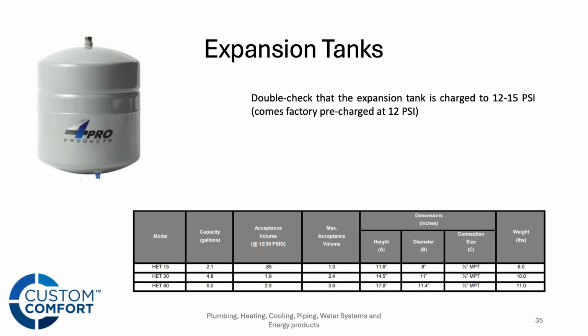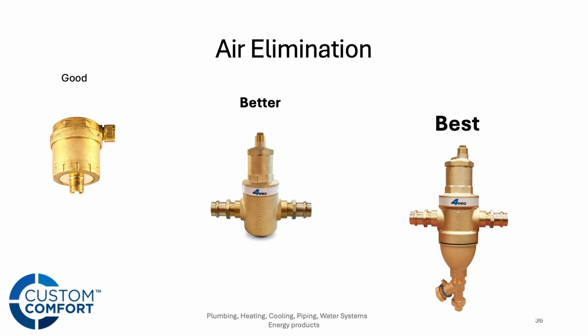Could keep going, talking about garbage disposals and tub drains and all that, but we're here to talk about hydronic boilers tonight. So these are our 4Pro expansion tanks, right? We've got a 15, a 30, and a 60. Gonna need one of those on every boiler. We've also got our own air elimination. So if you want to throw an air scoop in with a high vent, we've got that. I prefer to see our air eliminator in the middle there. Or even better, we've got an air dirt mag combo.